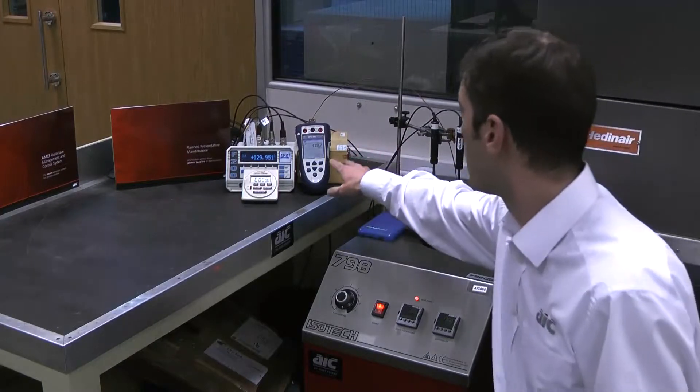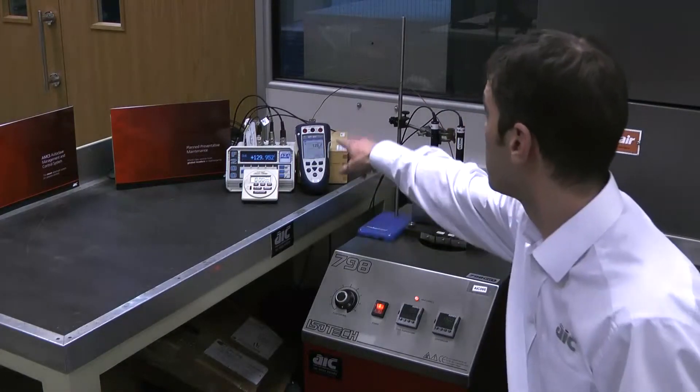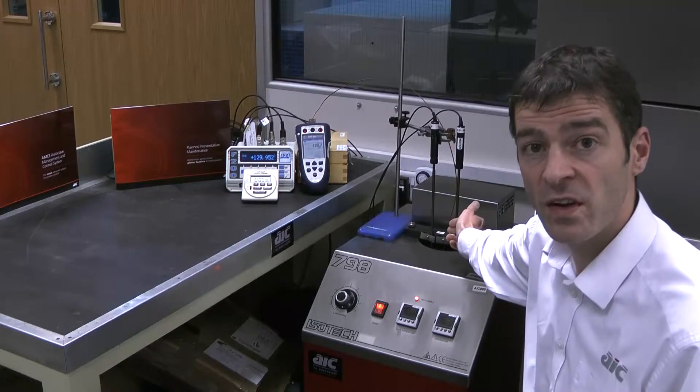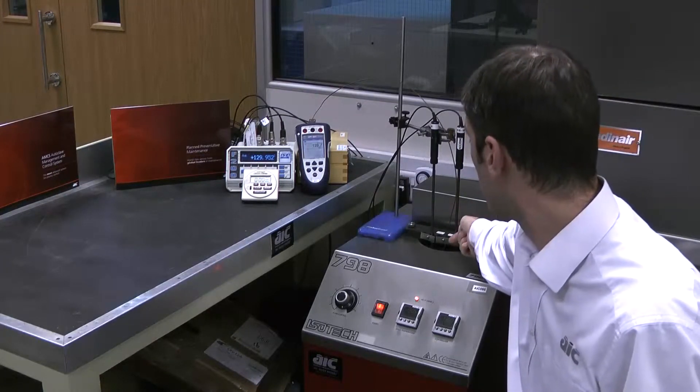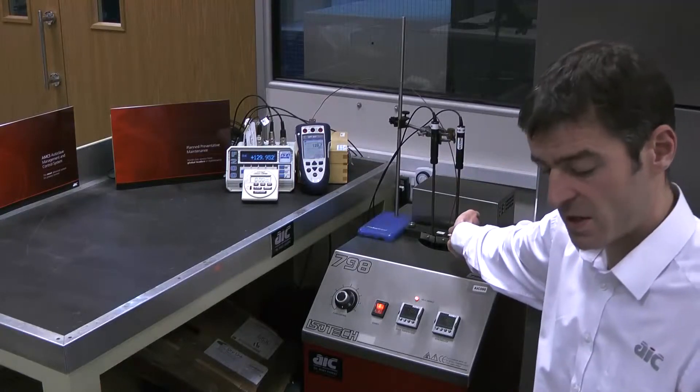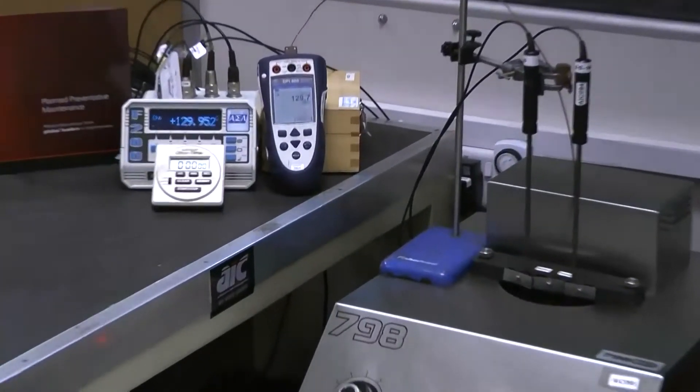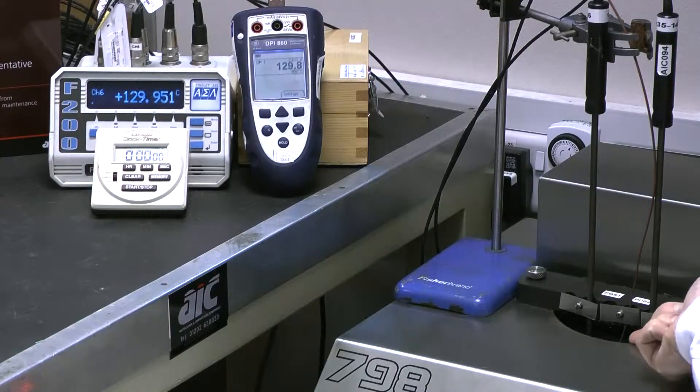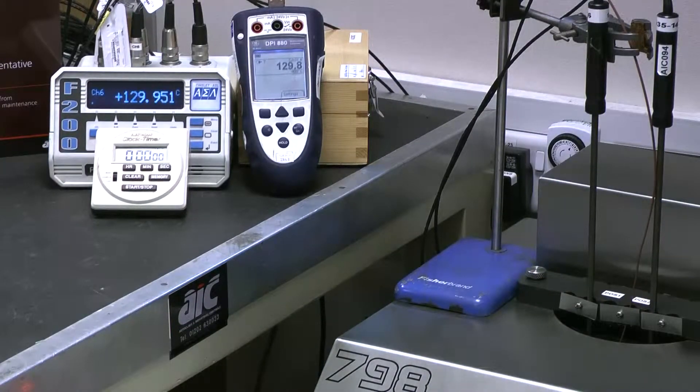And then I have a process calibrator connected to a Type T thermocouple at the moment, which is inserted in the oil bath. And you can hopefully clearly see that the portion of the thermocouple that's entering the oil, just down here, is indeed the Type T thermocouple.